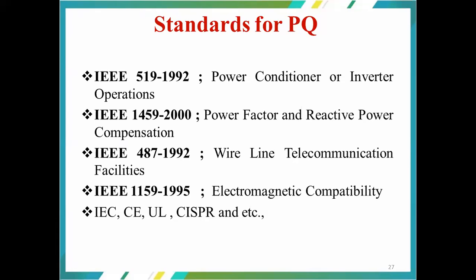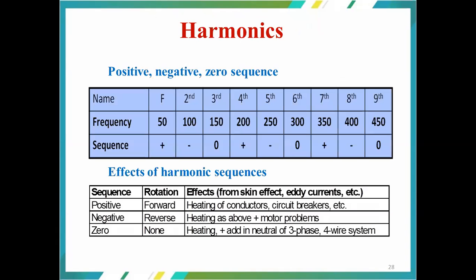So all these standards are region specific, product specific, or country specific, meant for the safety of the equipment as well as the safety of the consumers. The next one is harmonics. In that we have positive, negative, and zero sequence harmonics. Positive sequence means forward rotation. Negative sequence means reverse rotation. Zero sequence is the neutral condition, which has neither forward nor reverse rotation.